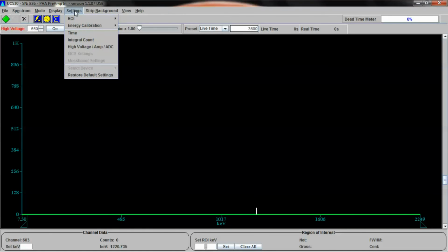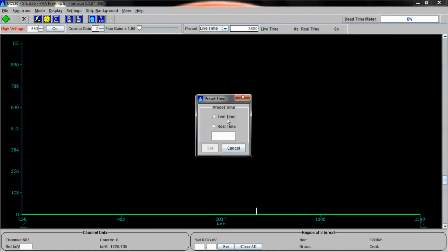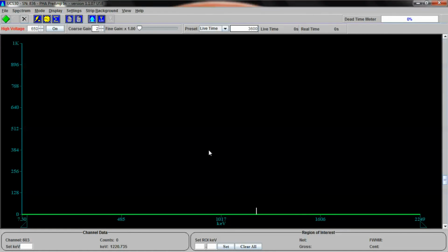All right, we're fully calibrated, ready to go. Let's go for setting time. Make sure it's set correctly, 3600 seconds. Time is about 5:30, so it will be done at about 6:30, plus or minus. Everything is away from the detector that could cause impurities in what we're seeing. Let's start it. All right. And we are in linear mode, and we'll change that to the lowest setting we can get so we can see.